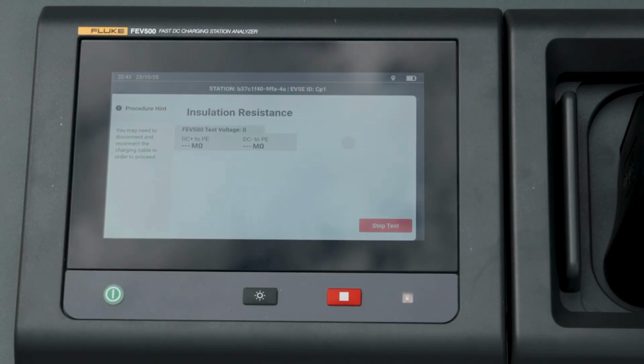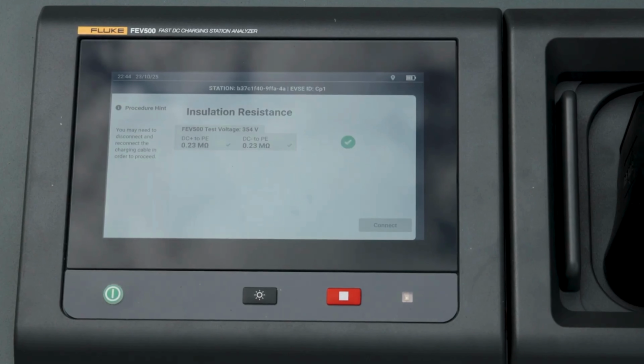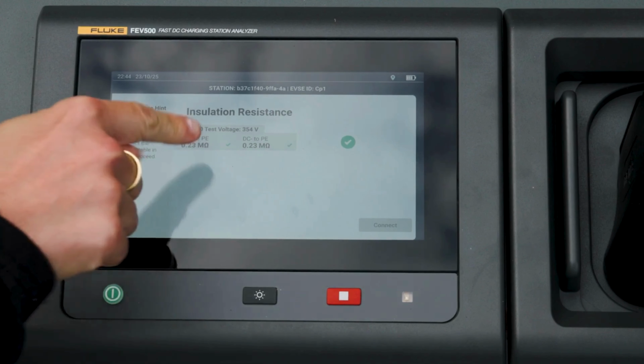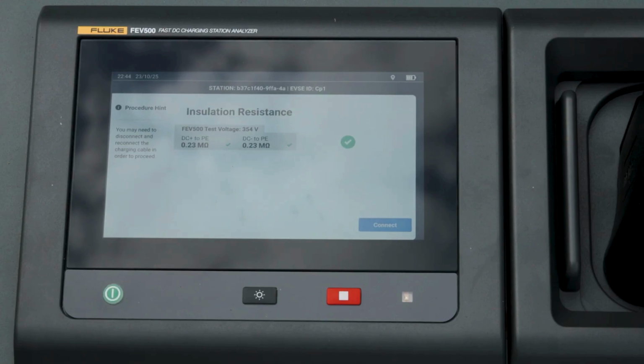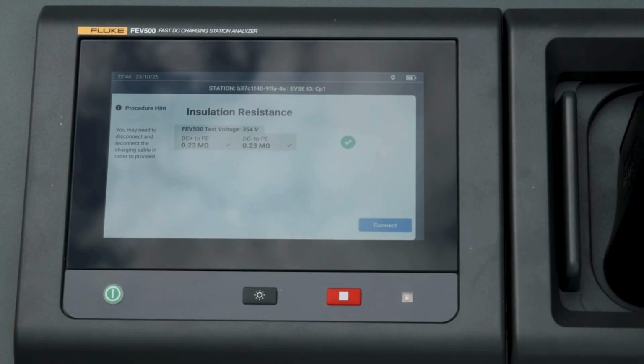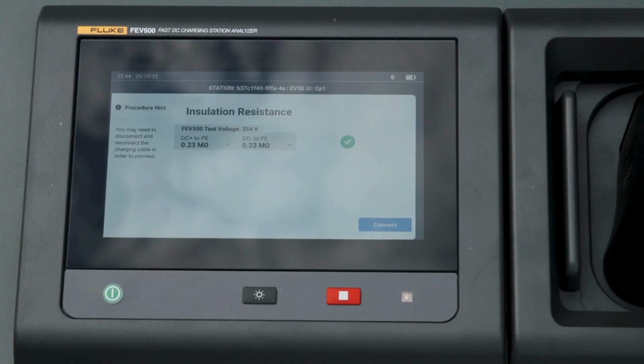And now it's testing the insulation resistance. So running an insulation test on the output of the charging station. And you can see here we're testing between DC positive and PE, or protective earth, and DC negative to PE. Perfect, and you can see we got an individual pass indication on the DC positive and DC negative measurement, and then an overall pass. So you will see all of your pass and fail indicators on each measurement. Okay, next I'm going to hit connect.